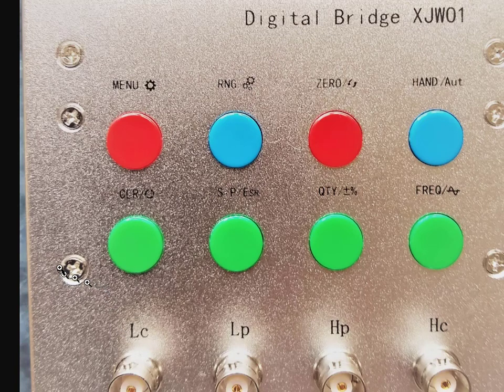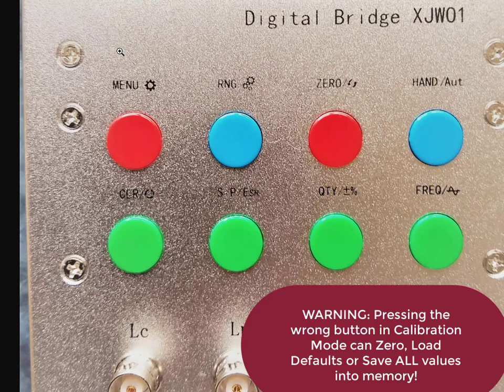Okay, and the last thing we need to talk about is the calibration mode. So there are 19 parameters which are stored internally in the memory, and it's possible to load the defaults or clear the internal parameters, and also to save the defaults. So the first thing you do is you press the menu key and hold it down for 3 seconds, and then the display will change, and then press the range button and you'll now be in calibration mode.